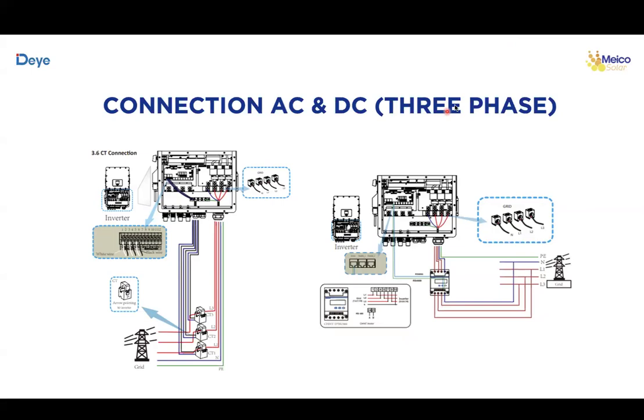I have a question as well from Henrik: if I have a project at 15 kilowatts with a grid of 120/208 three-phase, how many hybrid inverters are needed, and what type? In this case, for a 15 kilowatt project you will use only one inverter, Henrik, and that inverter will be, for example, the 12 kilowatt inverter that goes directly to that specification of grid, as in this diagram of connection. So you have three lines, a neutral, and the ground — basically you go directly, you don't need any other accessory or equipment. That's the way you would go for the project you mentioned.